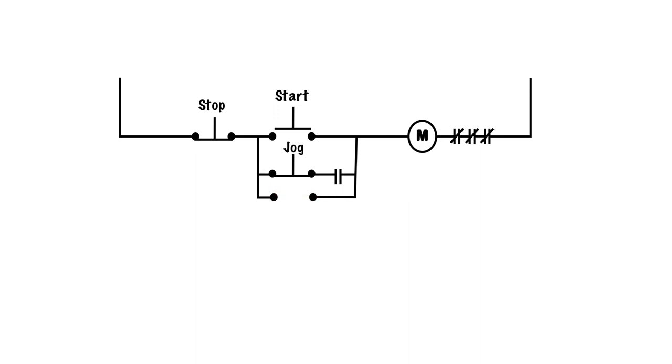And that can cause a problem which we'll discover later on in the video. So going through the regular start sequence, we press the start button down, we make contact, power can get through to the M coil. M coil energizes, which in turn closes these normally open contacts.